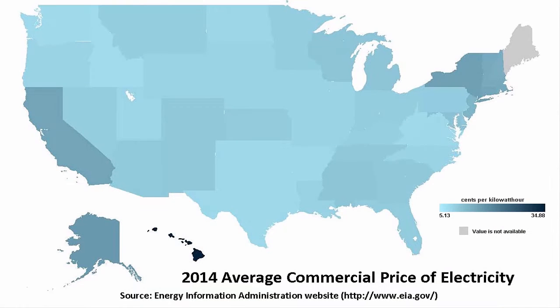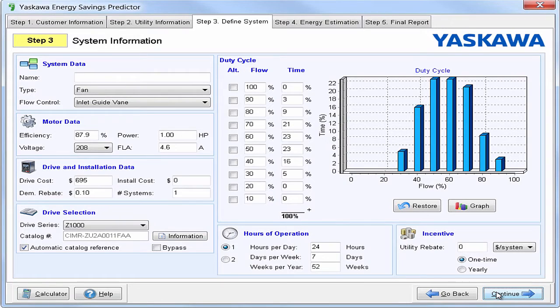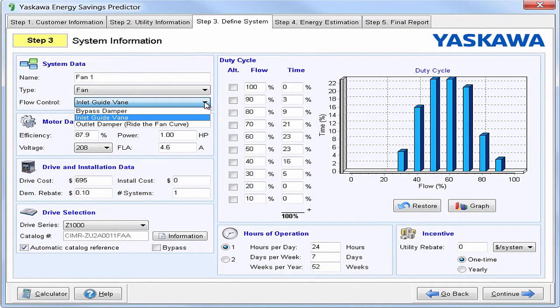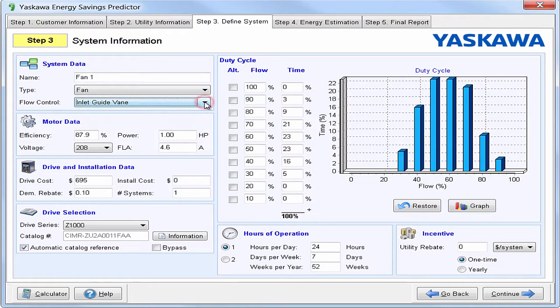This is a map of the average commercial price of electricity in 2014. As you can see, if you live in Hawaii, your electricity could be up around 35 cents, whereas some parts of the US could be as low as 5 cents. Utility information and system information are two of the most important steps in this predictor. Just start by naming the system. And since we chose a fan, we just need to select our flow control. That can be an inlet guide vane, a bypass damper, or an outlet damper. The inlet guide vanes tend to be more efficient than the outlet damper.